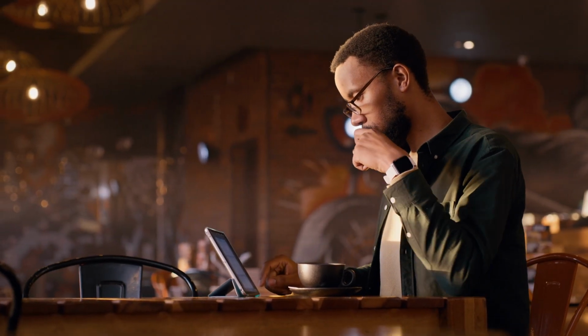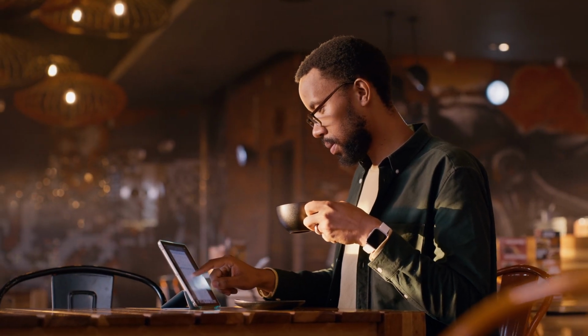Think about the inverse square law of airflow, and then just the sheer volume of space in a modern warehouse. Massive. Right, so if you have a single rack generating a massive thermal load, pumping cold air into the general vicinity means a huge percentage of that cooling energy is just wasted. Well, chilling the empty aisles, the ceiling space, racks that aren't even running hot. Right. And worse, you run into what we call the bypass airflow problem.